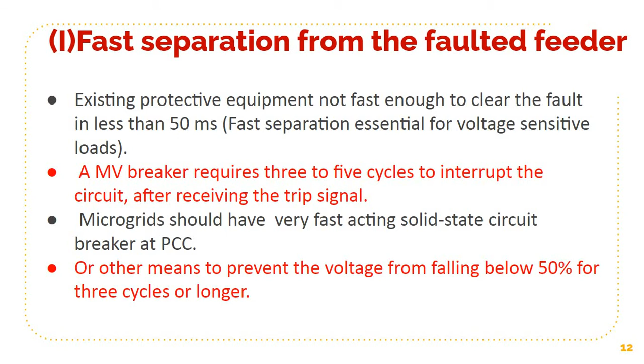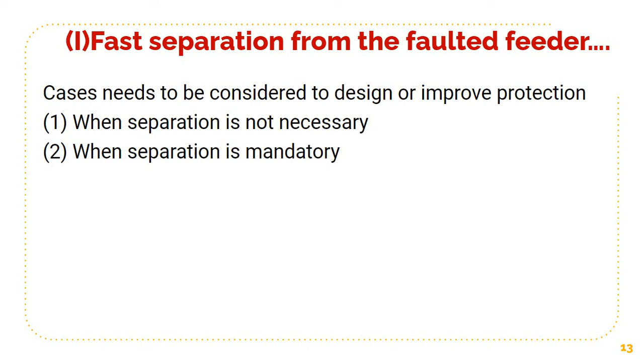So microgrids should have a very fast acting solid state circuit breaker at the PCC or other means to prevent the voltage from falling below 50% for 3 cycles or longer. The cases which we need to consider to design or improve protection are: number 1, when separation is not necessary, and number 2, when separation is mandatory.